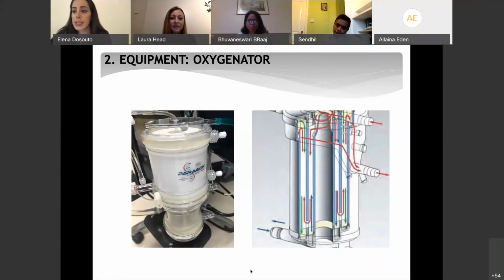So an oxygenator basically is an artificial lung that allows CO2 and oxygen exchange similar to the one in the alveoli. And we also control the temperature with the oxygenator, which is great. So to start with, you can see here on the right the graph of the path of different things across the oxy. So the blue one is going to be the water, the green lines is the gas, and the red is obviously blood. So first of all, the blood passes through the heat exchanger phase, and this is because if there is like a massive change of temperature, some bubbles might come out of solution. So you want that to be absorbed first, if that makes sense.